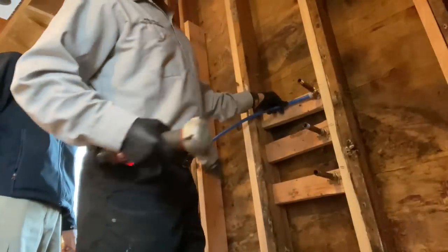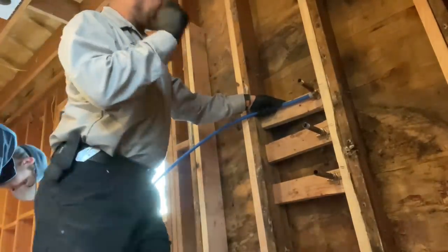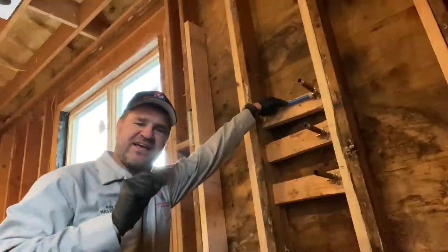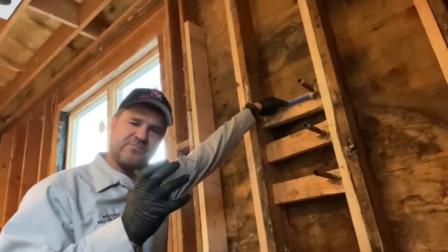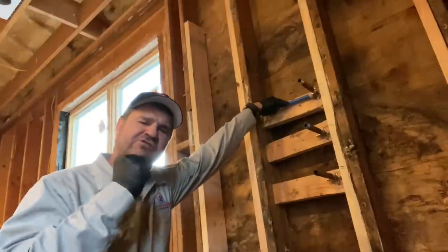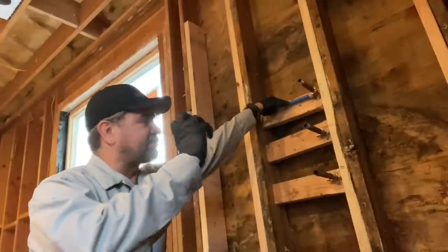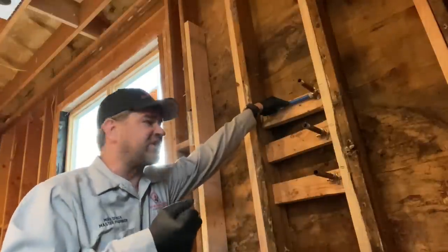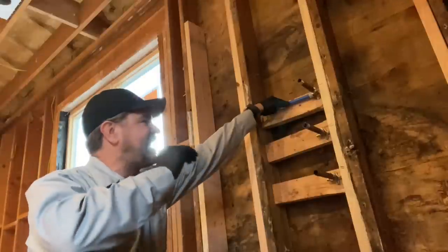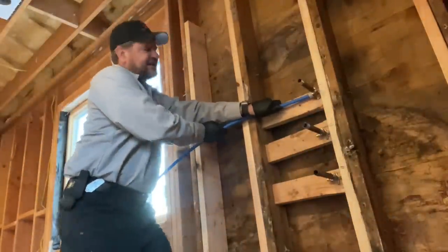Five times. Slide it over there for a 10 count. And the great thing about expansion PEX A, sorry, now you can see me, is that when you expand it, it expands to the size of the PEX tool, and it's going to spend its entire life trying to get back to that original size. And that's the purpose of that ring, to give that added security so it's not going to want to come off. So the expansion ring is at the end of the PEX. That expands as long as the PEX, and it will spend its entire life trying to go back to that size. So when I try to pull on this, it's not going to go anywhere.